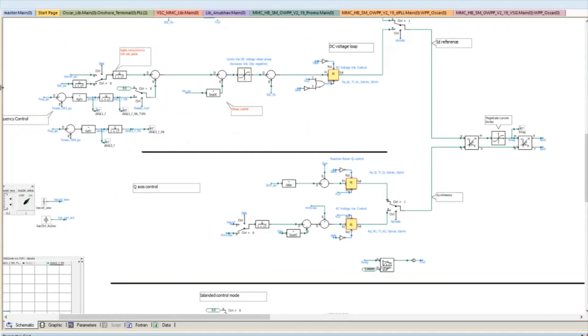Additionally, this frequency control has been implemented, which basically means that if there is a deviation on the onshore frequency due to, say, load changes, that would be communicated to the offshore frequency via this change in the HVDC link DC voltage. And this is to basically use the wind power plant also for supporting any frequency deviations on the onshore side without any communication links, but using the HVDC link as the communication variable.